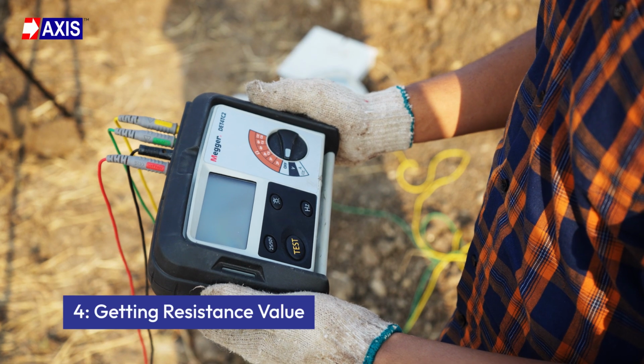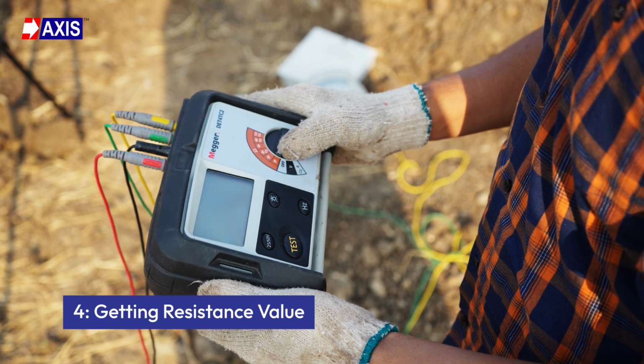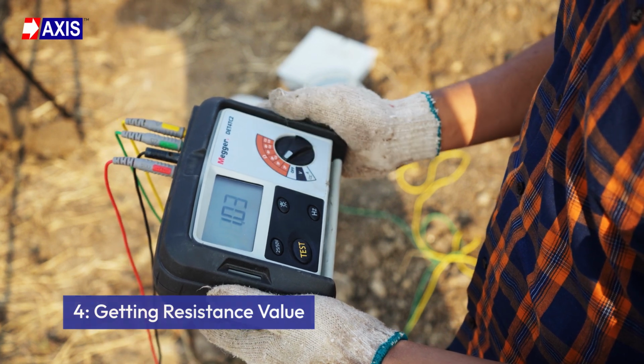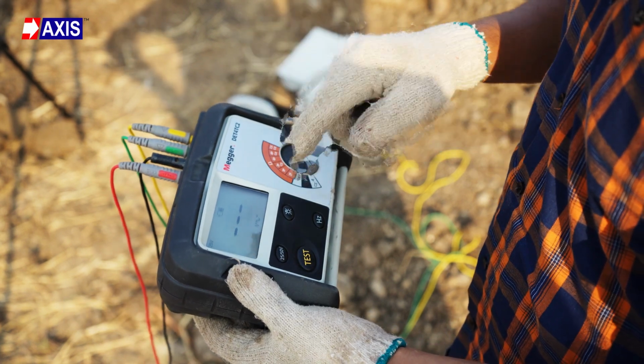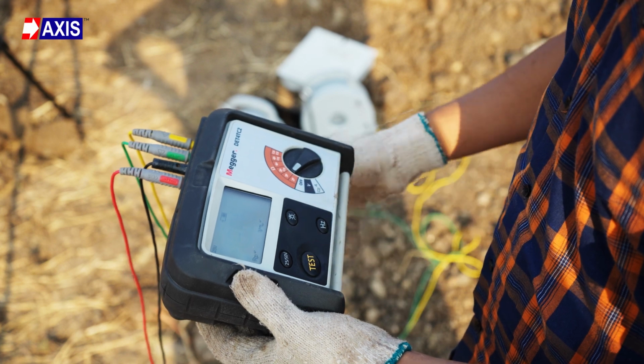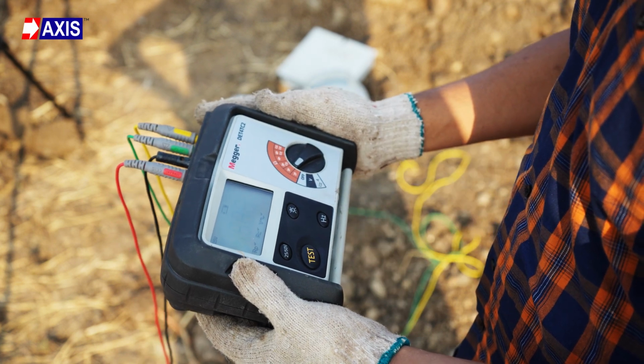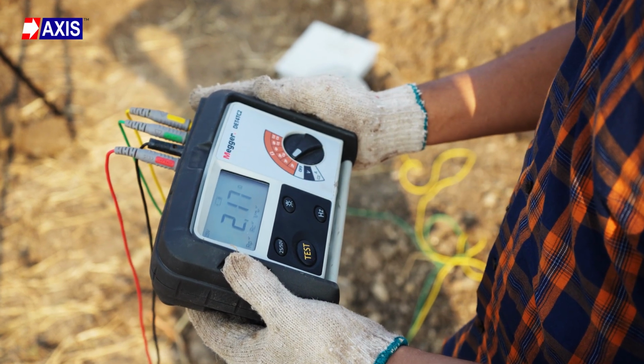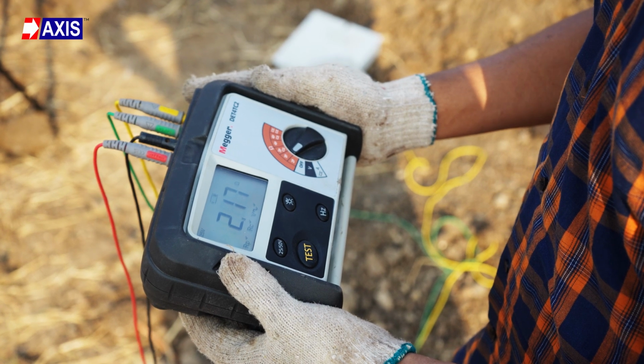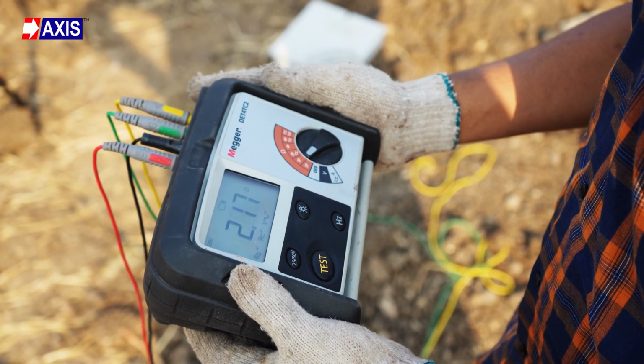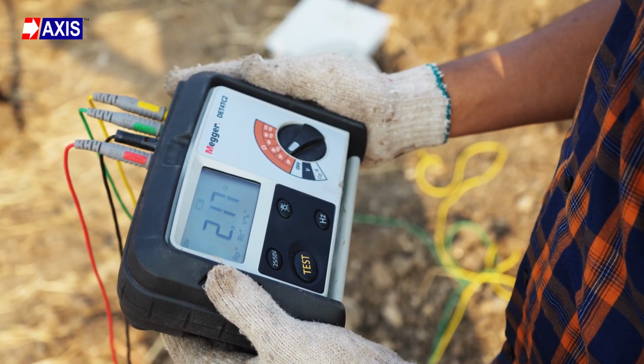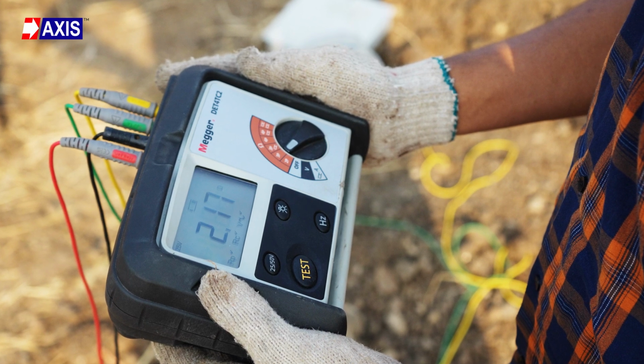Step 4. Get the resistance value. Set the rotary switch of the tester to the 3-point method. Now press the test button. The tester will display the resistance value of the earth electrode. This reading represents the true resistance value using the 61.8% method. I hope you now have a clear understanding on how to measure the resistance.